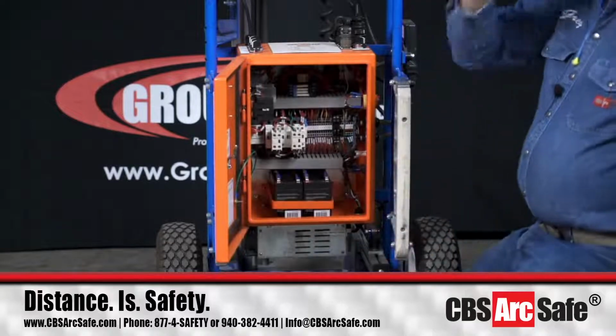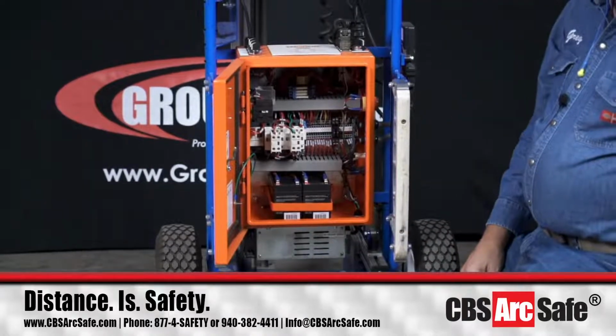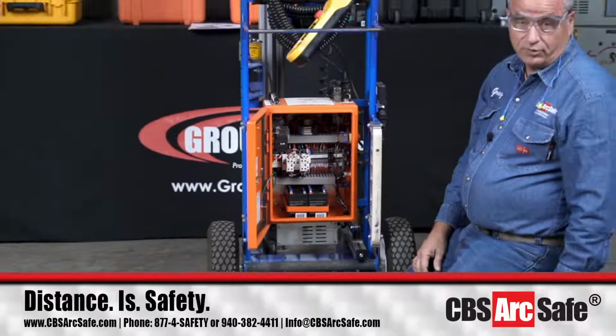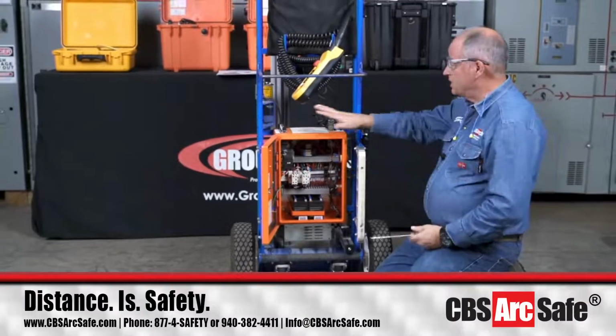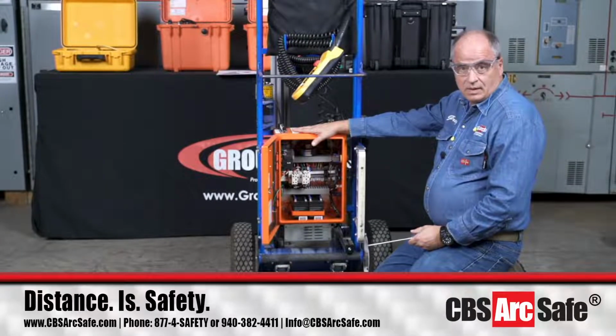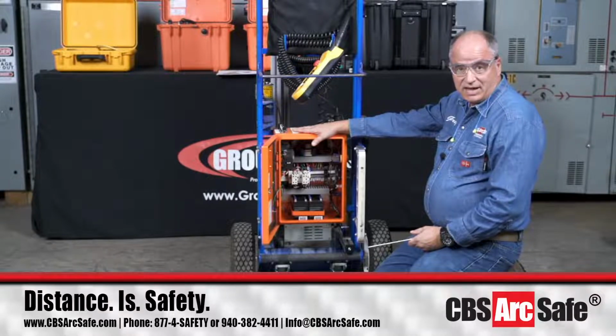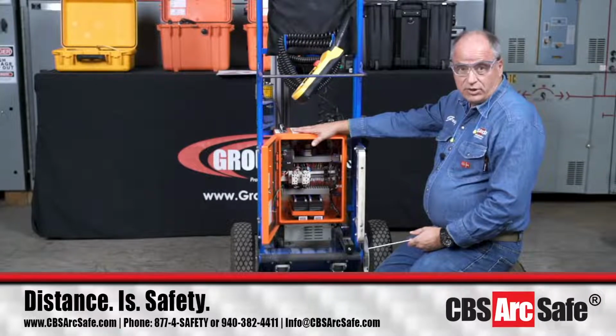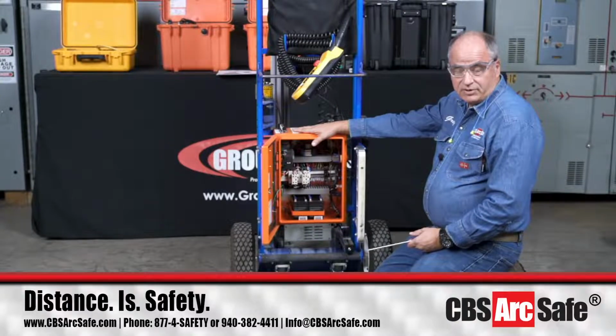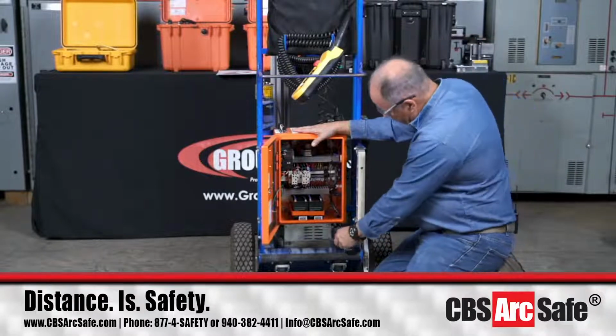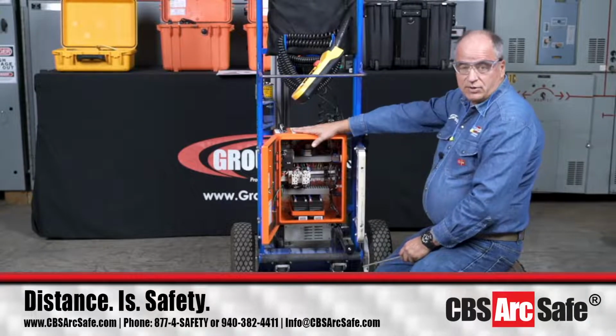That's all it takes to replace the batteries on an RS1, RS2, or RS4 unit. Now, things to note: the CCM module would tell you on the RS1 and RS2, it would give you a minus BA indication, telling you that you have one racking operation left and you need to recharge the batteries. When you inspect these batteries, if they're not holding 12 volts on each battery minimum, then you need to replace them.